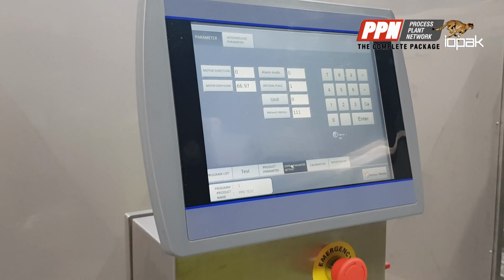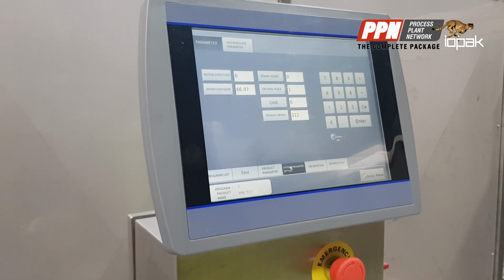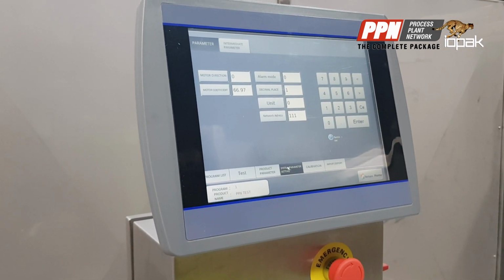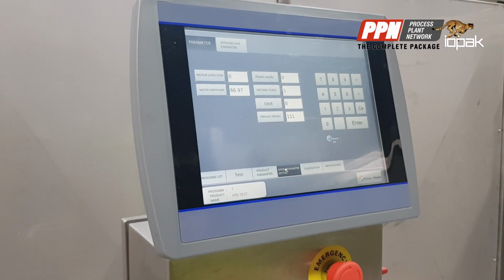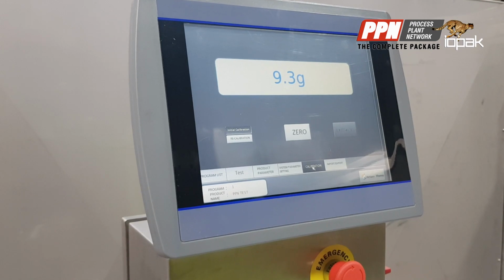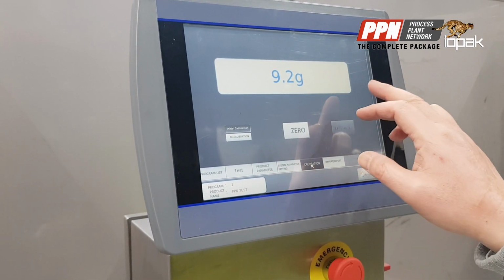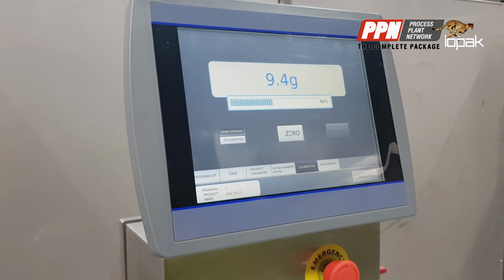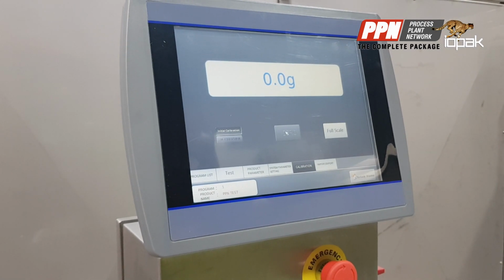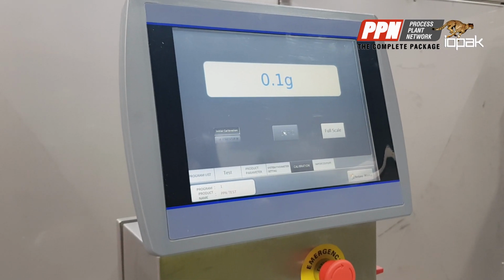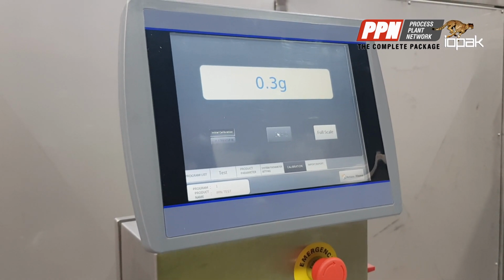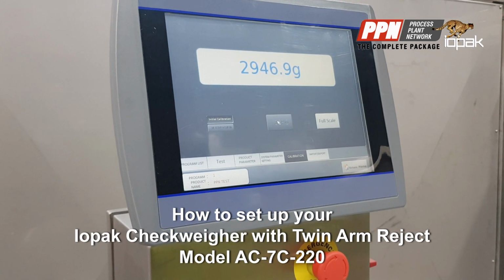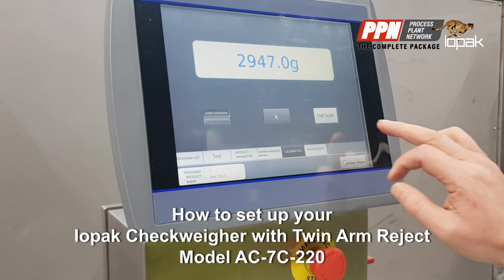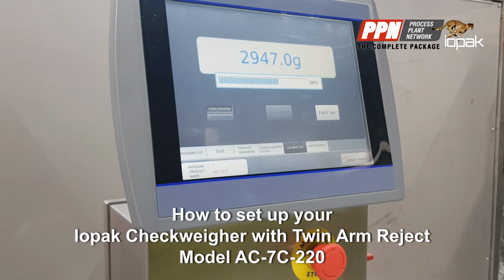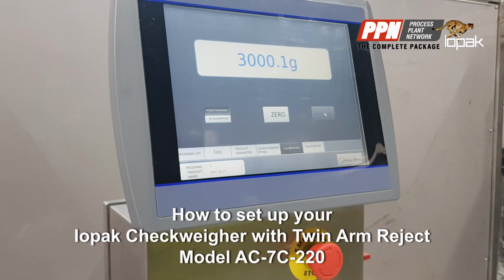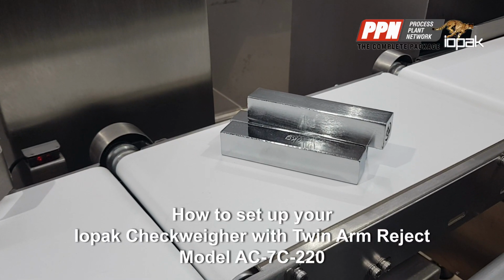Next, what I want to show you is the calibration of the weigher. This particular checkweigher has a 3 kilogram limit, so we do need to calibrate it with a 3 kilogram sample weight. It is relatively simple. Initially, you just press 0 and wait. When this is done, we put the 3 kilogram weight in. After you put the 3 kilogram sample weight on the weight bridge, press full. Now the calibration is complete.